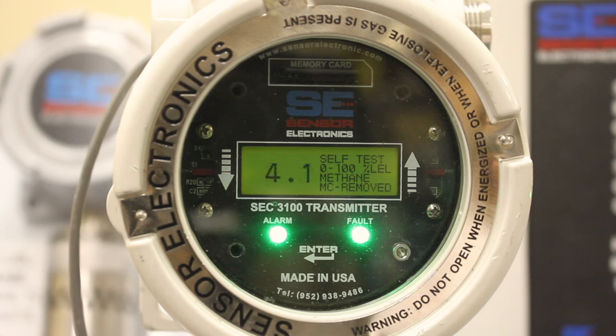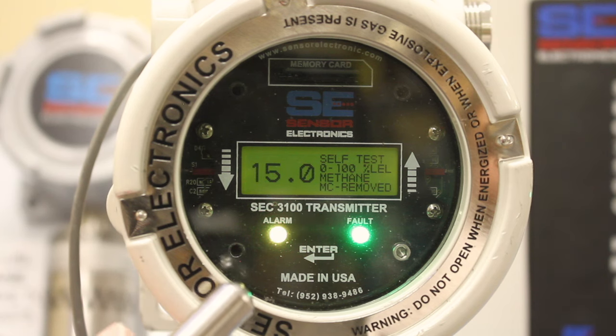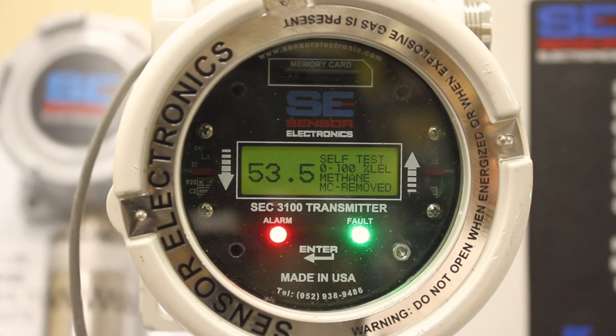The self-test just ramps the signal up from 0% LEL to 100% LEL, and then you can see the different alarm levels. Once it reaches a low alarm, it turns yellow, and then once it reaches the mid alarm, it turns orange, and once it reaches the high, it will turn red. And then it just continues all the way up to 100%. And then it will just go back to normal operation. And up in the upper right hand corner you can see that it's indicating it's in the self-test mode. And this would trigger any alarms back at the 3500 controller that this sensor is connected to as well.